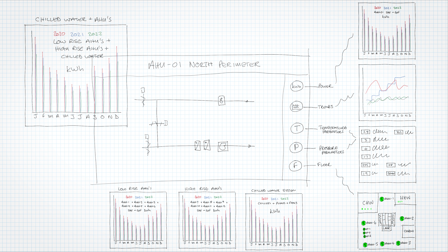For those buttons - the floor plan, parameter pages for temperature and pressure, the pre-configured saved group of trends, and the AHU power performance dashboard - that data already exists in the BMS generally. All of this is just a matter of drawing a graphic and linking it to a button. You don't have to spend any money on buying anything, assuming you have a BACnet connection to a VSD. This is what I consider just good practice - what we should have already. I have this on my jobs, except the power widget which I just created this morning.